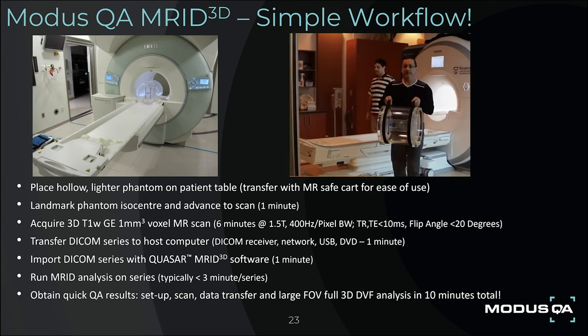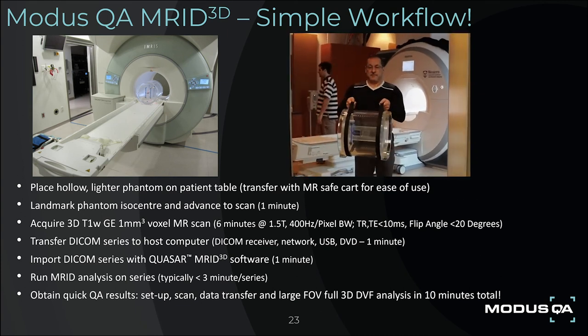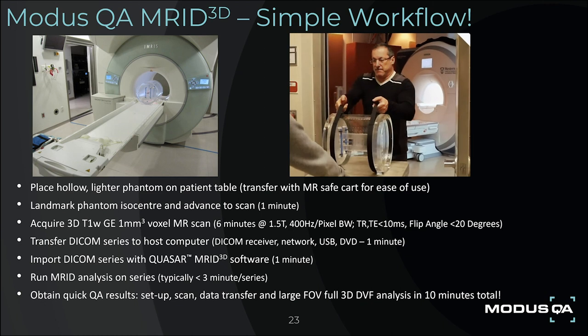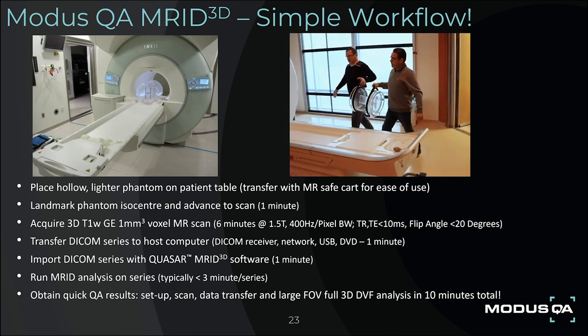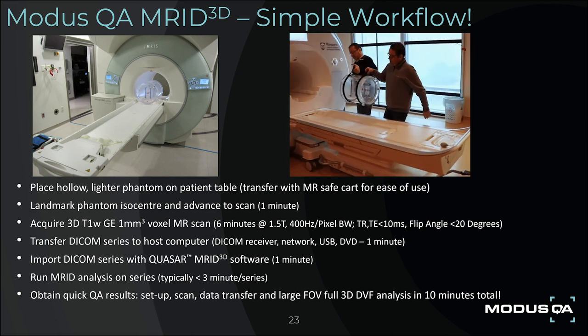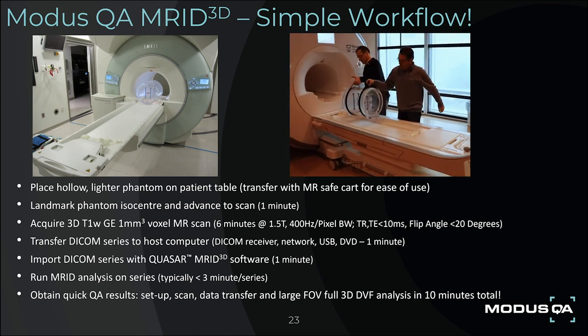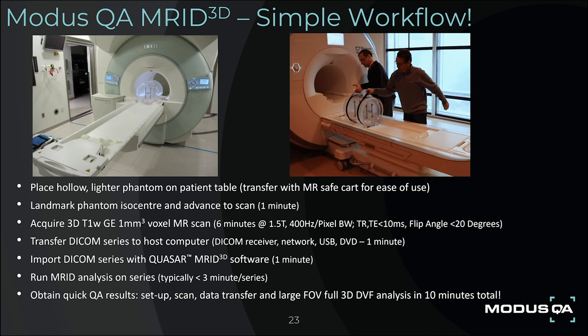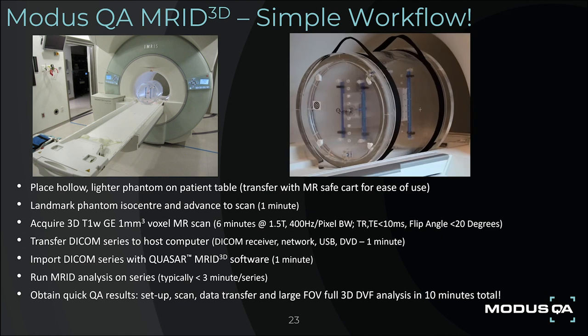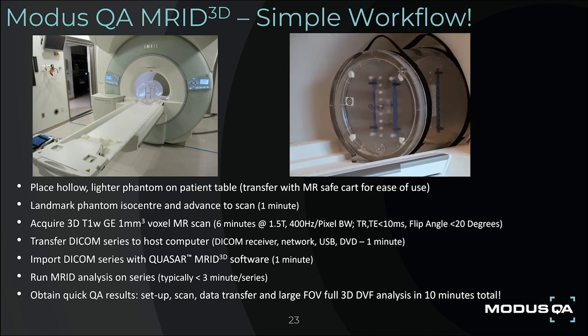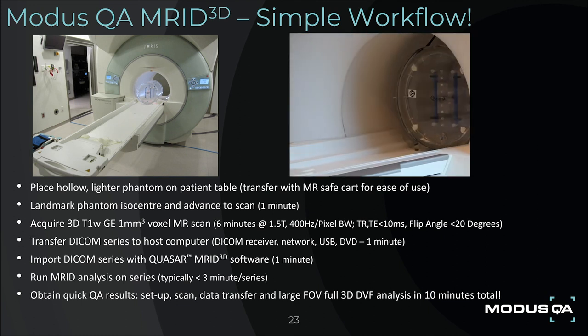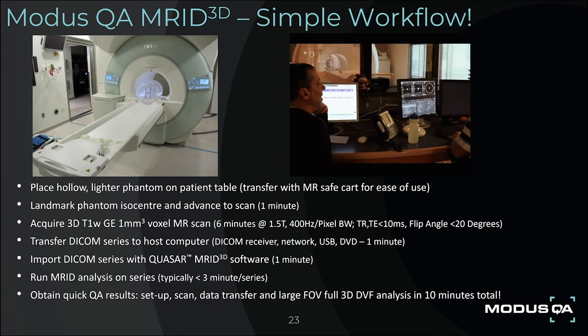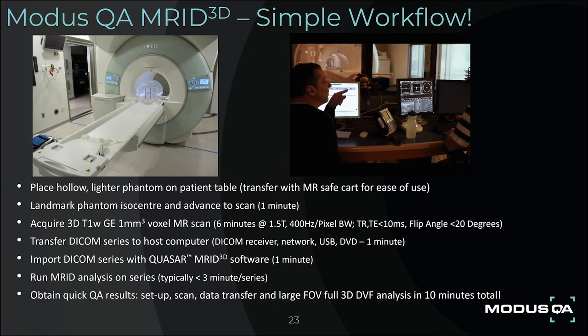Import the DICOM series with Quasar MRID 3D software in under a minute and run the analysis, typically less than 3 minutes per series. In this way, one can obtain quick QA results from setup, scan, and data transfer, obtaining a large field-of-view full 3D DVF analysis in 10 minutes total.